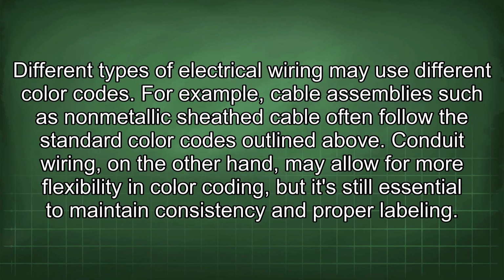Different types of electrical wiring may use different color codes. For example, cable assemblies such as non-metallic sheath cable often follow the standard color codes outlined above. Conduit wiring, on the other hand, may allow for more flexibility in color coding, but it's still essential to maintain consistency and proper labeling.